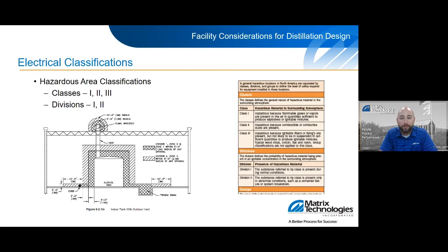These ratings do drop the further you get from the source. The image I have here on the screen is taken out of Discus. So it kind of shows the classification bubble around the equipment. So you can see here you've got the Class 1 Div 1 radius around the tank and into lower lying areas, and then your Class 1 Div 2 kind of goes around that bubble, as well as your exhaust points on the flame arresters or conservation vents. That bubble does grow a little bit. So the further away from the equipment, obviously the better your classifications get, or the less stringent they become.